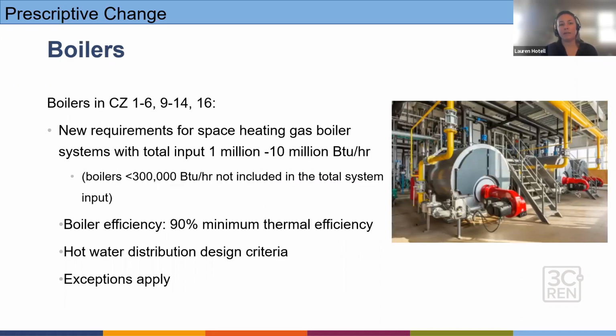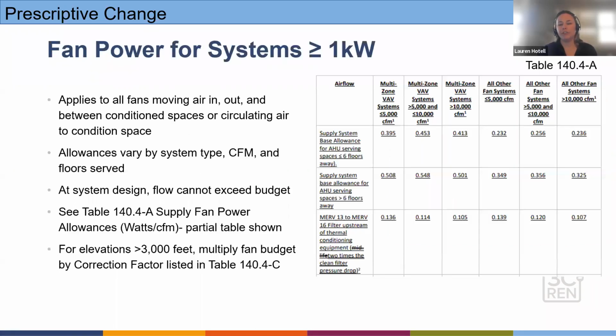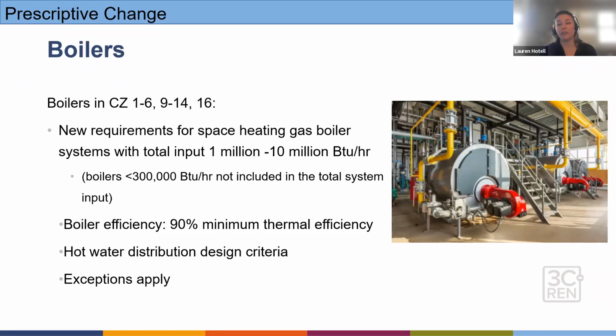Boilers: in climate zones 1 through 6, 9 through 14, and 16, there's a new requirement for space heating gas boiler systems. This also requires a 90% minimum thermal efficiency. To achieve this 90% efficiency, some or all of the boilers must have condensing capability. Boilers within the same building but on separate loops are not considered part of the same system. There are exemptions that apply, so take a look. The coils and other heat exchangers must be designed for a hot water return temperature of 120 degrees Fahrenheit or less, and the flow rate is reduced to less than or equal to 20% of the design flow of the operating boilers.